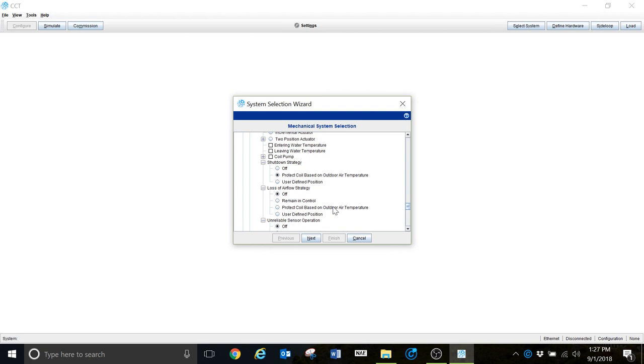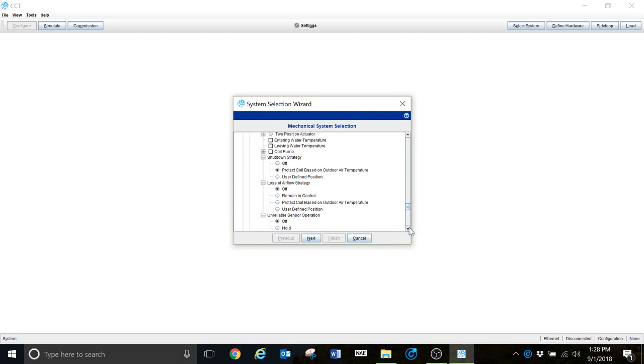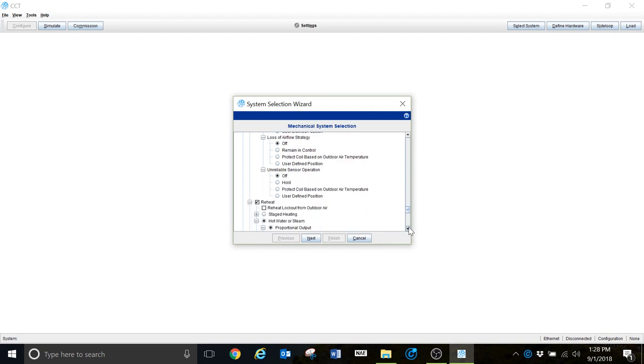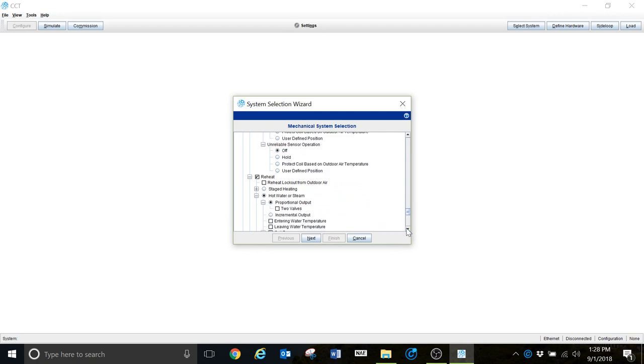Generally with the weather patterns here, we only have a couple of units where we maintain chilled water flow on trip, simply because of the size of those units and the coil configuration. Maintaining that flow on a unit attached to a central chilled water plant in super cold conditions can help. Systems attached to their own chiller we will just drain, so we don't have as much to worry about with freezing a coil — but again that depends on how your system is configured.